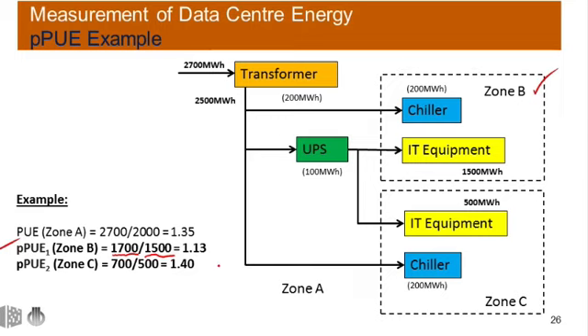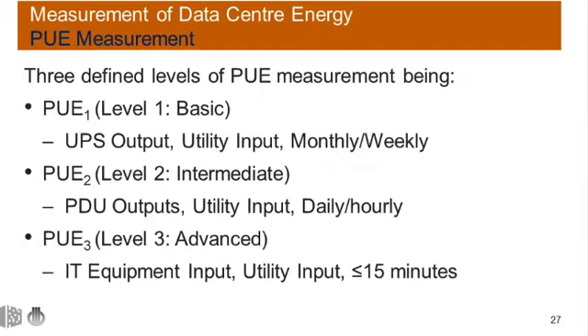Partial PUE2, being zone C, shows 700 divided by 500 equaling the 1.4 PUE. The 500 being the IT load again, plus the 200 megawatt hours indicated in brackets of the chiller. This equates to 1.4 PUE. Now, if we look at the overall facility as a whole, going back to zone A again, we have a PUE of 1.35. So you can see, depending on how PUE and partial PUEs are reported, there can be some significant differences in the outcomes.